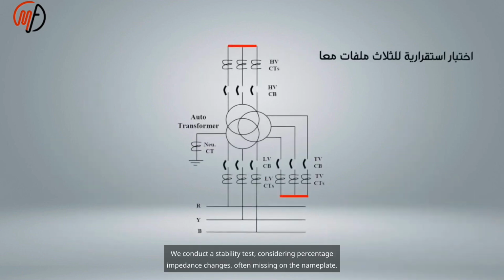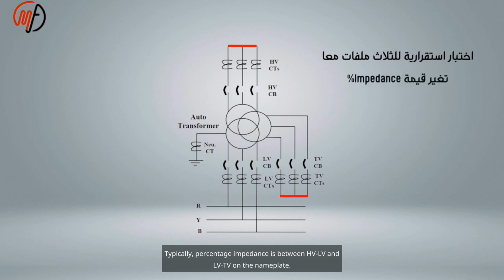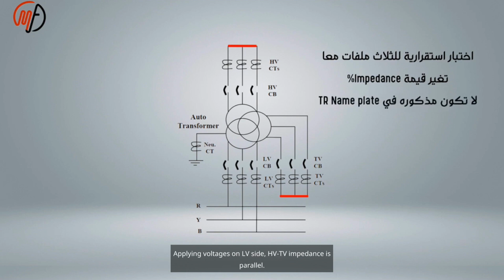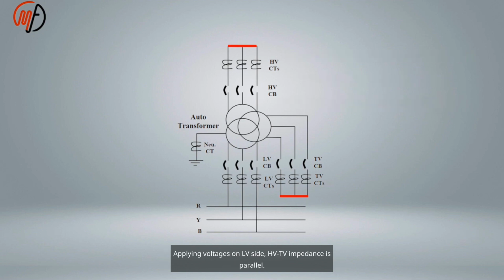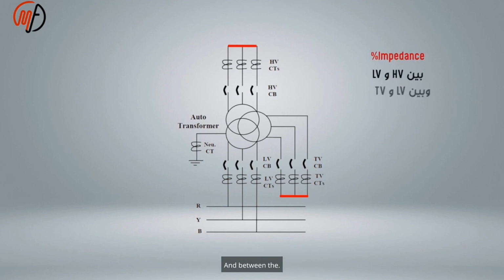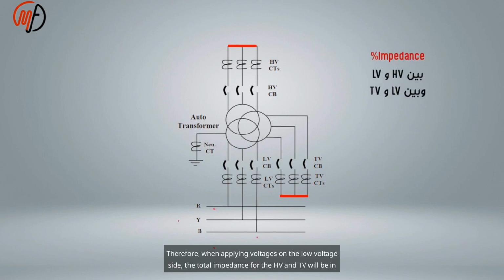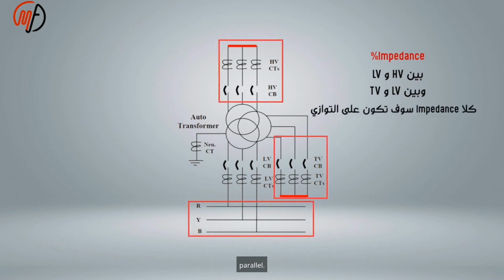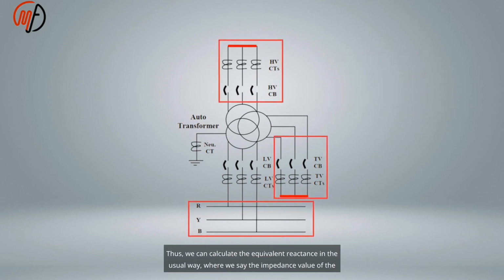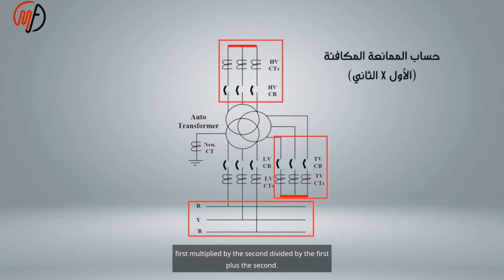We conduct a stability test considering percentage impedance changes, often missing on the nameplate. Typically, percentage impedance is given between HV-LV and LV-TV on the nameplate. Applying voltages on the LV side, the HV and TV impedances are in parallel. Calculate the reactance: multiply the first by the second, divide by the sum. Therefore, when applying voltages on the low voltage side, the total impedance for the HV and TV will be in parallel. Thus, we can calculate the equivalent reactance in the usual way, where we say the impedance value of the first multiplied by the second divided by the first plus the second.